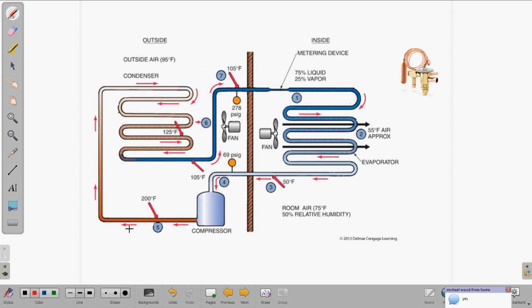Okay. And a lot of times, if that's happening, okay, Scott, adjusting the TXV, that's probably the last thing you want to do. I want you to think about this. If you add refrigerant or adjust the TXV, it's 15 minutes in between an adjustment, and you're talking quarter turn adjustments.